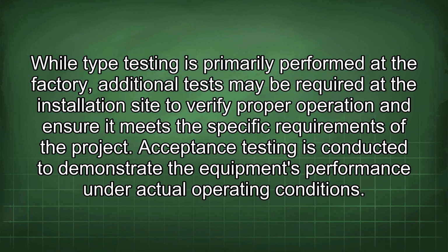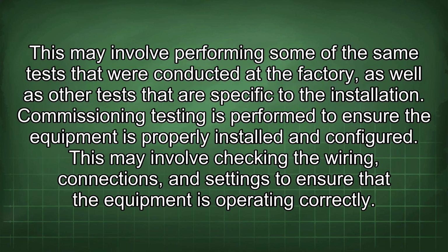While type testing is primarily performed at the factory, additional tests may be required at the installation site to verify proper operation and ensure it meets the specific requirements of the project. Acceptance testing is conducted to demonstrate the equipment's performance under actual operating conditions. This may involve performing some of the same tests that were conducted at the factory, as well as other tests that are specific to the installation. Commissioning testing is performed to ensure the equipment is properly installed and configured.